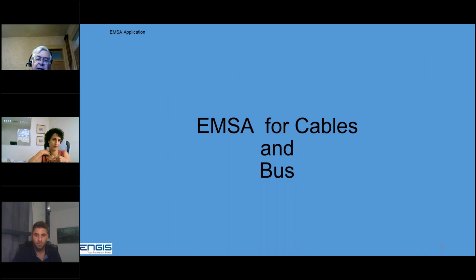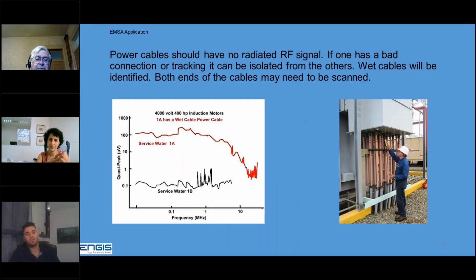You can apply EMSA to power cables and either isolated phase bus or non-segregated bus. Power cables do not have mica insulation. They should have no PD going on, so there should be no radiated RF signal from them. So here we are testing at a transformer at a plant with many generators. Here's the cables going in, and you can use the sniffer and check each one of these cables. If there's one that has a problem, both in the terminations or in the cable itself, that will stand out so you can determine which one is bad.